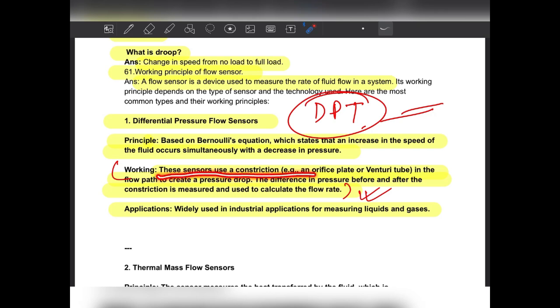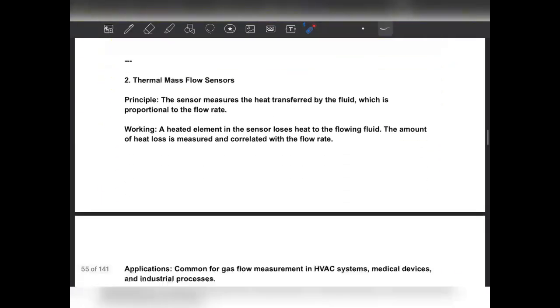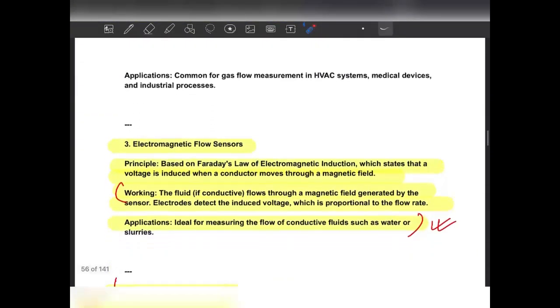Okay, this sensor uses a constriction, an orifice plate or venturi tube, in the flow path to create a pressure drop, and the difference in pressure before and after the constriction is measured and used to calculate the flow rate. Basically we calculate the flow rate from the differential pressure transmitter, and based upon that we are also controlling the flow rate. Okay, this is the differential pressure transmitter, DPT type. I will explain later also.